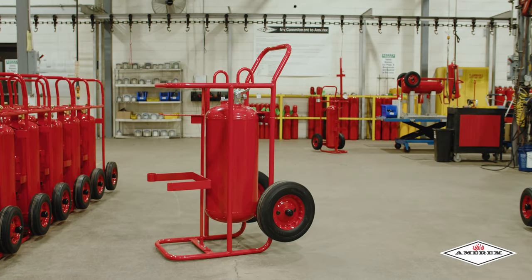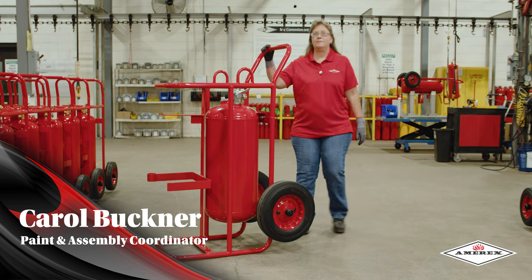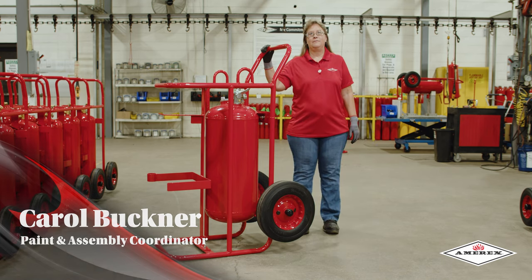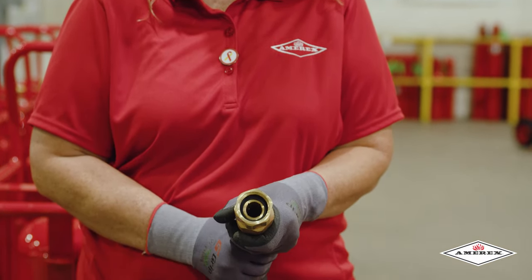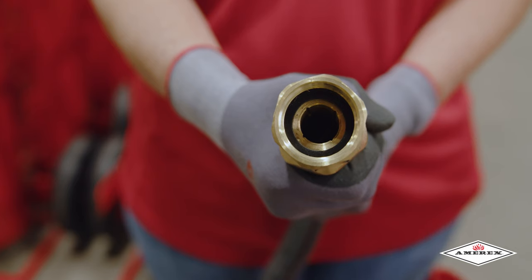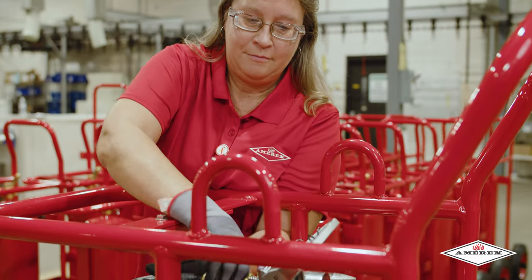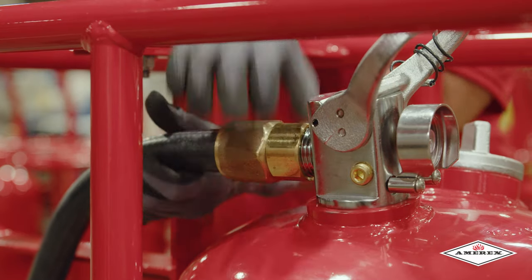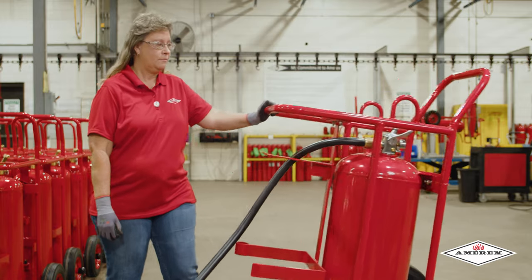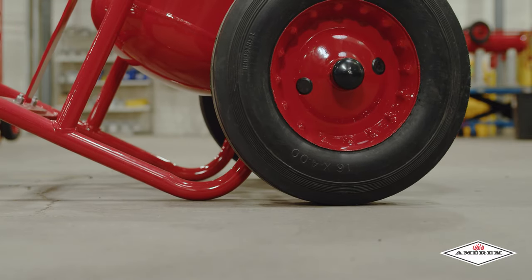Hello, I am Carol Buckner with AMEREX Corporation. Today I will be showing you the technique to rolling or coiling our hoses on our wheeled unit products. The first step is to check the inside of the hose for the gasket to make sure there are no cuts or any damage to it. After your inspection of the gasket, your next step would be to hand tighten your hose to your discharge valve. Lean the unit back on its wheels to make it easier to roll or coil the hose on the unit.